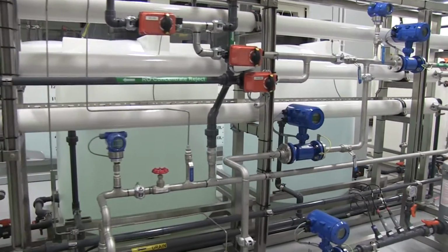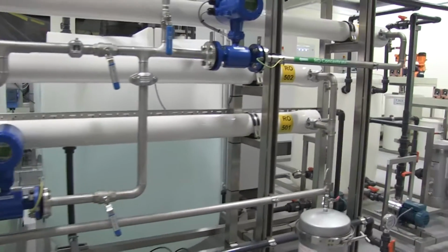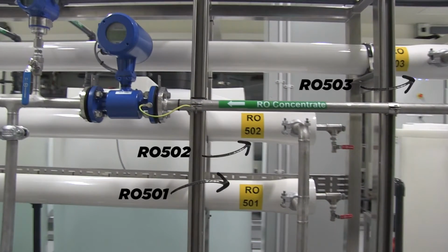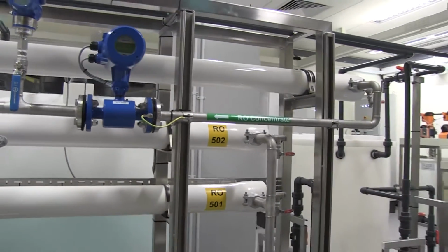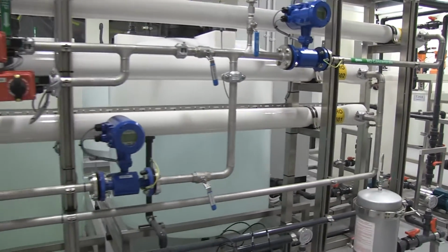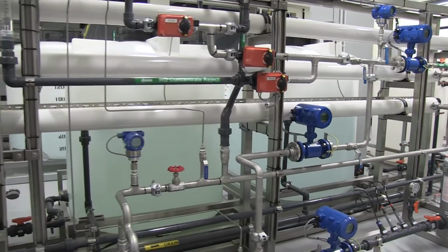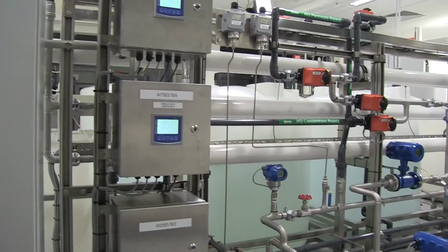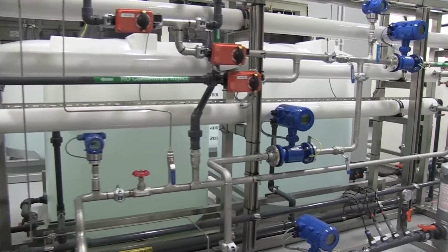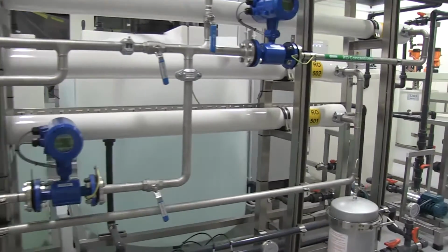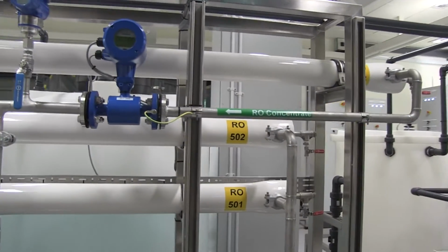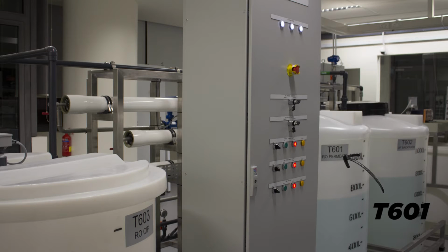Stage 5 controls a variable speed pump to feed water through a two-stage reverse osmosis unit labeled RO501, RO502, and RO503. This stage is by far the most complex of all stages in SWaT in terms of programming and physical design. The complexity arises due to the sensitivity of the nanometer membranes in the reverse osmosis unit to free chlorine and to any solid particles. Permeate from the RO unit is sent to tank 601 and the reject to tank 602. The permeate is recycled into the raw water tank. The reject is used to clean the ultrafiltration unit.